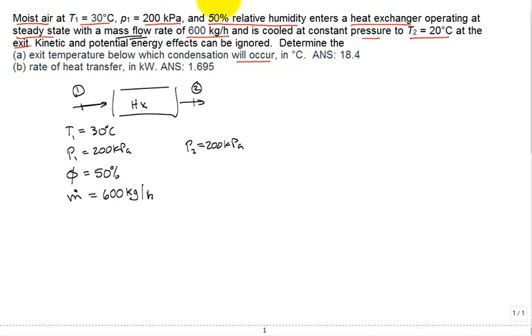The next thing we need to talk about are these pressures. Once you start solving heat transfer problems with moist air doing sensible heating, latent heating, or cooling, you really want to use the psychrometric chart. But at this pressure, it's not 1 atm. It's significantly above 1 atm, so you cannot use the psychrometric chart to solve this problem.